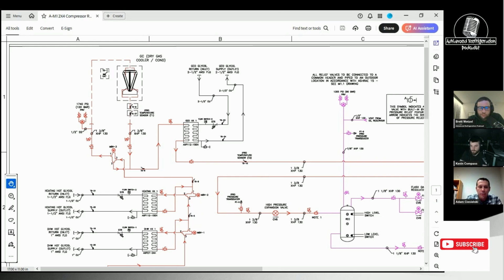And then what happens next? Now you have the high pressure valve, but that pressure continues to drop even if the fan's off. Then the high pressure valve starts to regulate to maintain a minimum discharge pressure. Think of a typical pressure system back in the days where you have a flooded condenser control. You've got the inlet pressure regulator valve, which maintains a minimum pressure. But as soon as that starts to close, you start to back up refrigerant in your condenser, and then you need a bypass to maintain your receiver pressure. The same thing happens here with CO2, but just with electronic valves. So the high pressure valve starts to maintain your minimum discharge pressure and starts to back up liquid. That liquid temperature coming out of the gas cooler is going to start to drop pretty quickly. That's when your bypass valve comes into play.